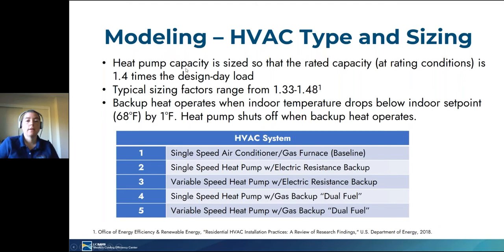As far as heat pump capacity sizing, we auto-sized the heat pump capacity so that the rated capacity at the rating conditions for the heat pump was 1.4 times the design day load. Typical sizing factors in construction are within the range of approximately 1.33 to 1.48, and so that's how we picked the 1.4 factor. And as I mentioned, the backup heat operates when the indoor temperature drops below the indoor set point, which was 68 degrees, and the heat pump shuts off when the backup heat operates.